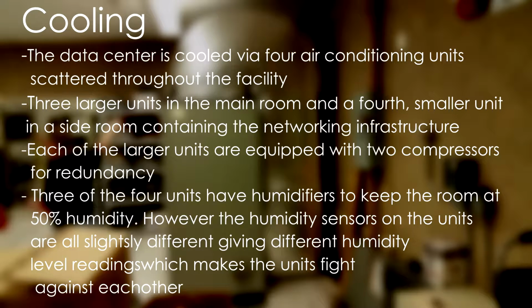3 of the 4 units have humidifiers to keep the room at an even 50% humidity. However, the humidity sensors on the units are all slightly different, giving different humidity level readings, which makes the units fight against each other.